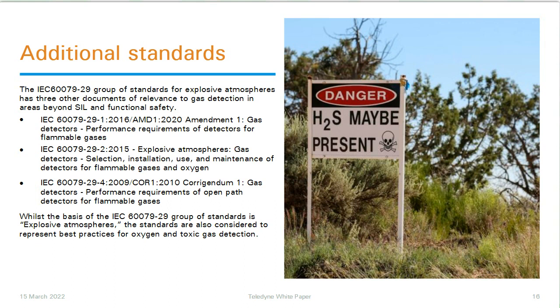Furthermore, that group of standards is specifically focused on explosive mixtures, but those standards are also considered to be best practice for handling oxygen, which itself is not explosive, but leads to other gases becoming more explosive and more flammable, and also toxic gases, some of which, such as hydrogen sulfide, are indeed flammable, many of which are not. So it's a very wide-reaching and useful group of standards for anybody involved in gas and flame detection.